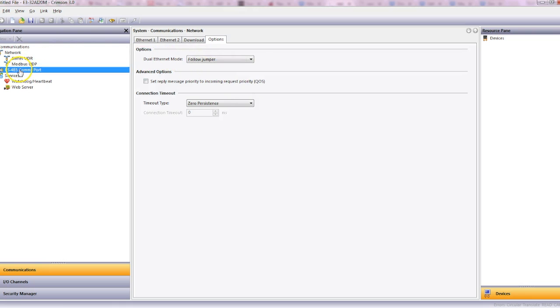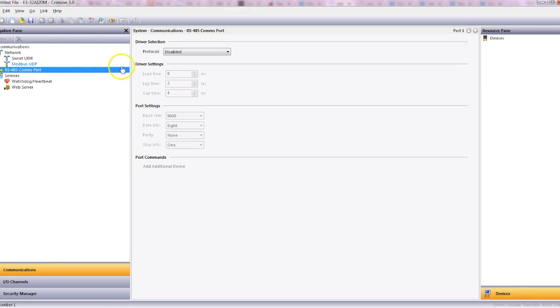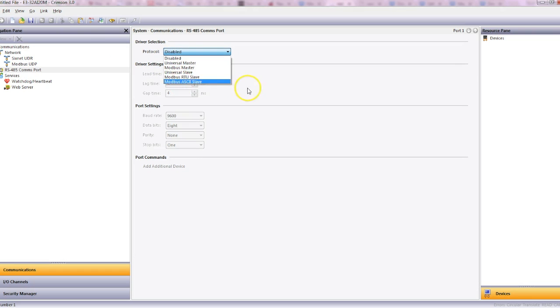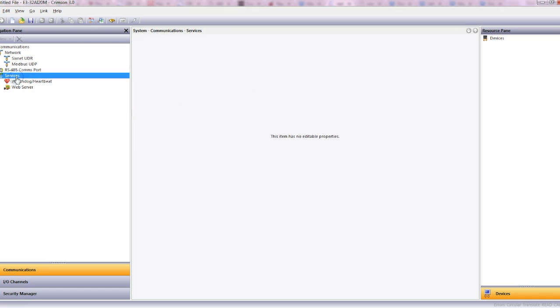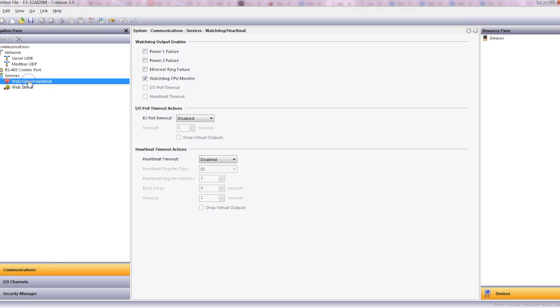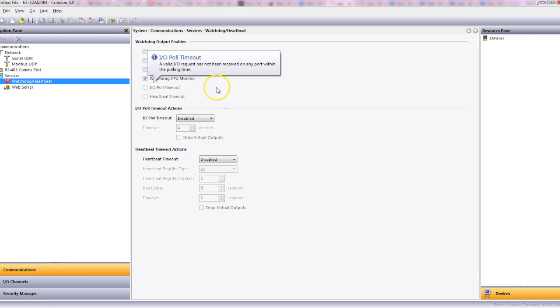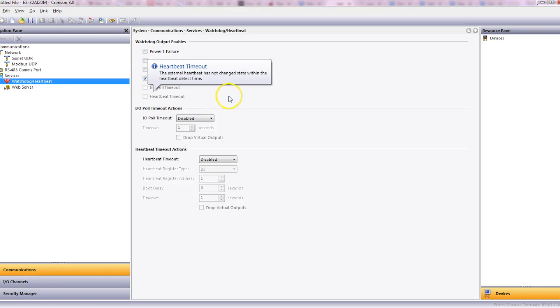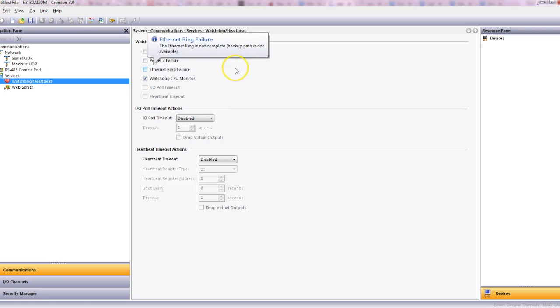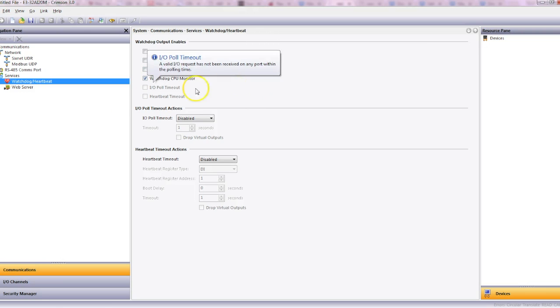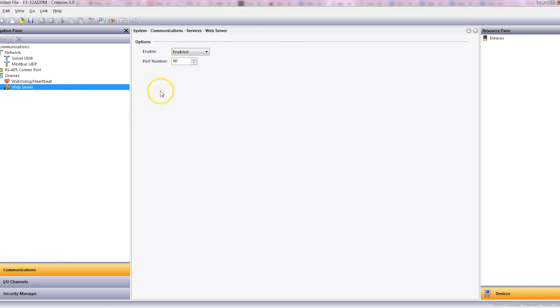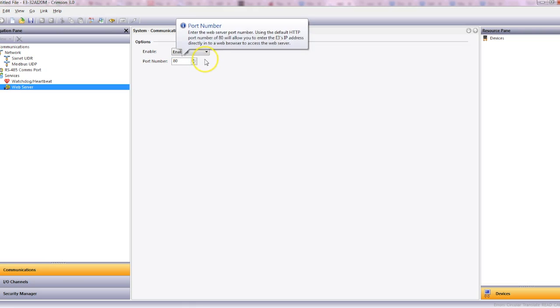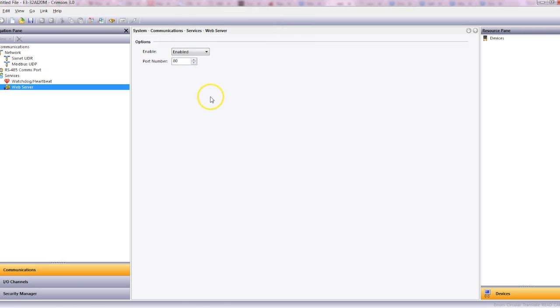We've also got a 485 port here. We can select the protocols we want to talk. For now we're not using it. Watchdog and heartbeat tick, those are really just a health status of the device itself so it responds back to the Red Lion HMI and tells it what's going on, which is good. Then we've got the web server itself, so we'll enable that. The web server enables you to see all the I.O. and the readings that it does and the status.